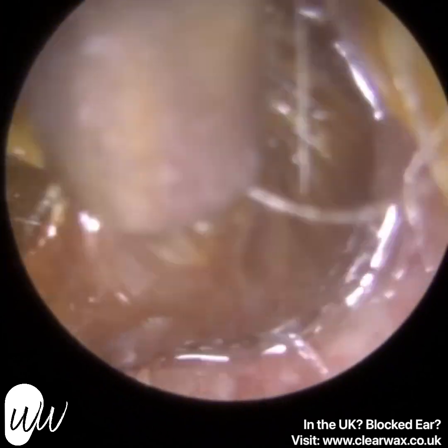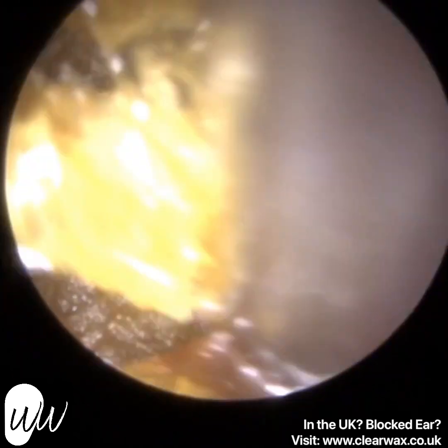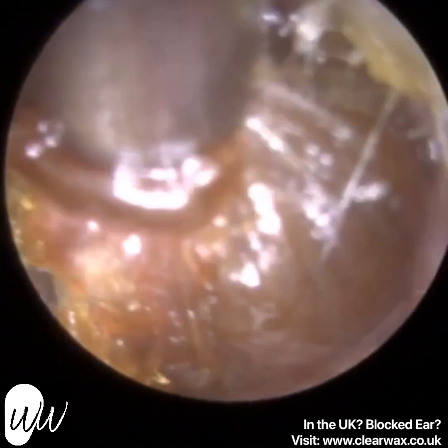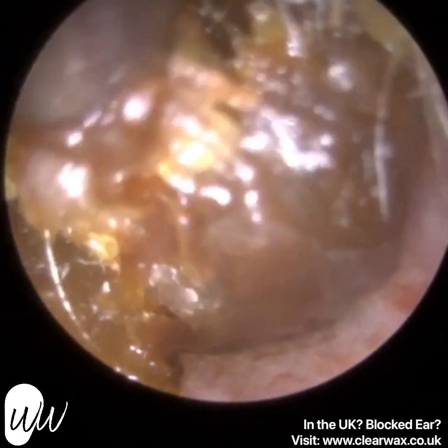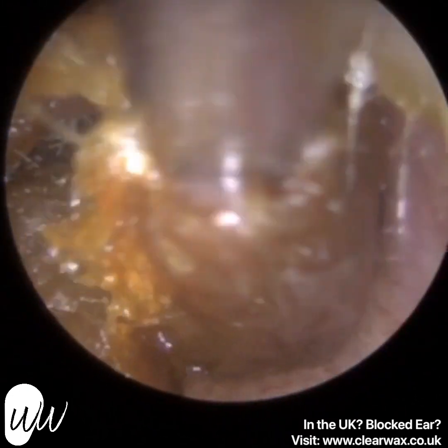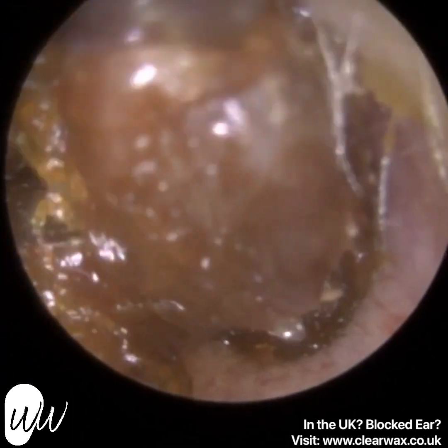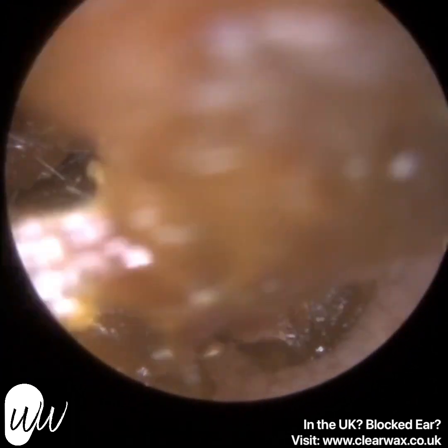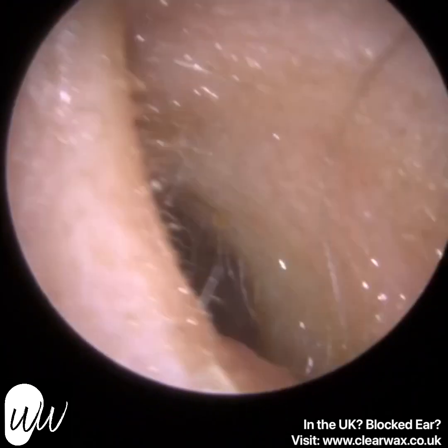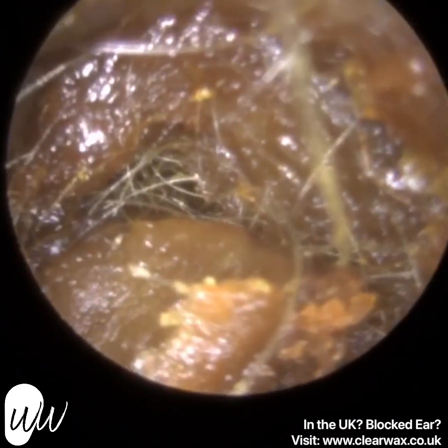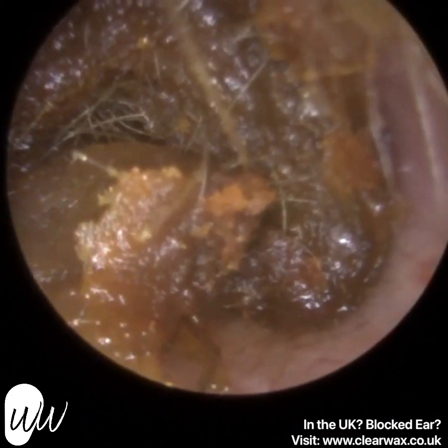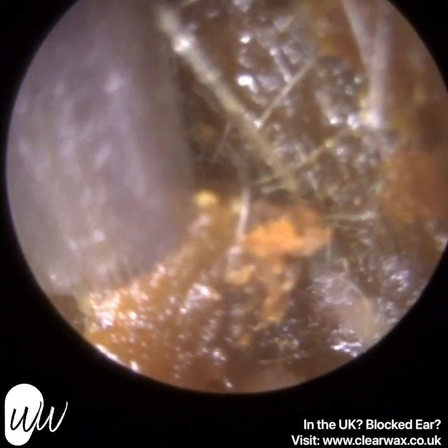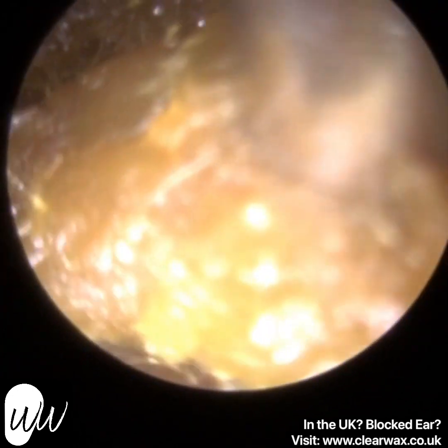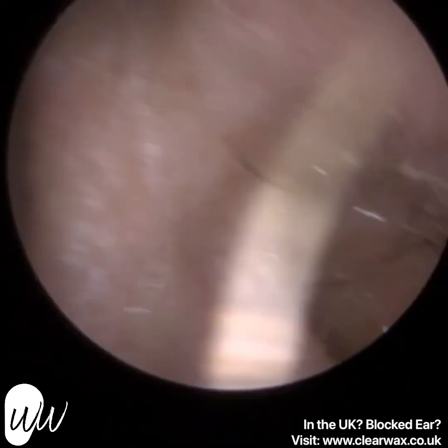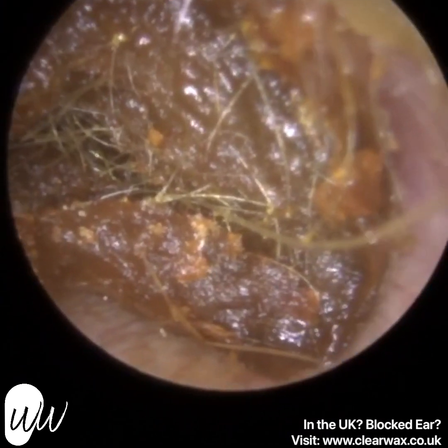I've just applied some olive oil spray into the ear just to lubricate the ear canal wall. And that's because this skin is strongly adhered, so I just want to help to loosen it. Also, the skin was somewhat blocking the suction probe. The oil not only helps to loosen the skin off the ear canal, but it is also designed to lubricate the inside of the suction probe, so any debris, wax or skin that travels through it doesn't get blocked.